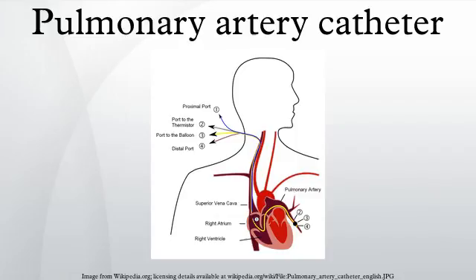One further development in recent years has been the invention of a catheter with a fiber-optic based probe which is extended and lodged into the ventricle wall, providing instant readings of SVO2, or oxygen saturation of the ventricle tissues. This technique has a finite life as the sensor becomes coated with protein and it can irritate the ventricle via the contact area.